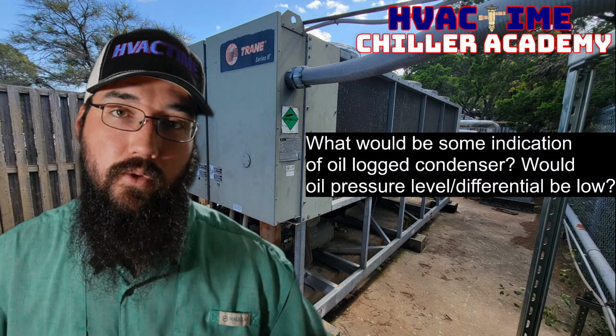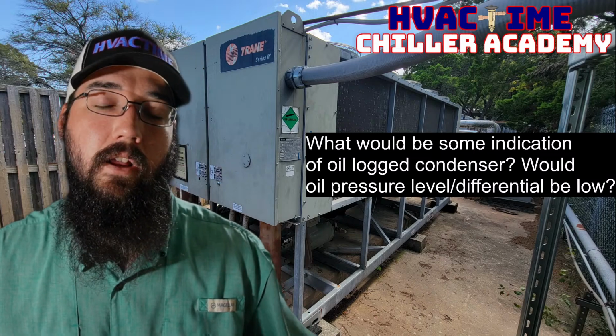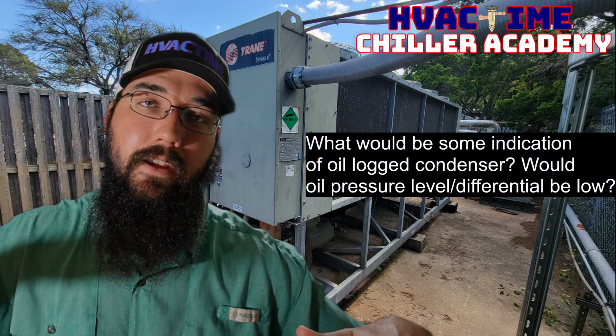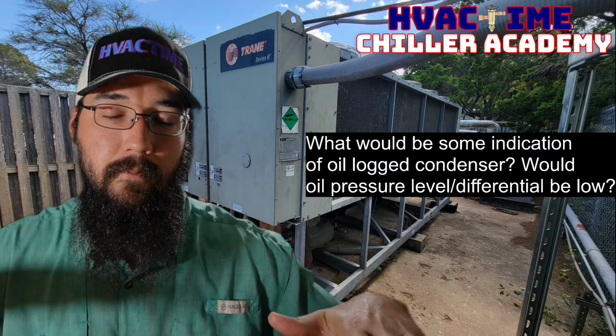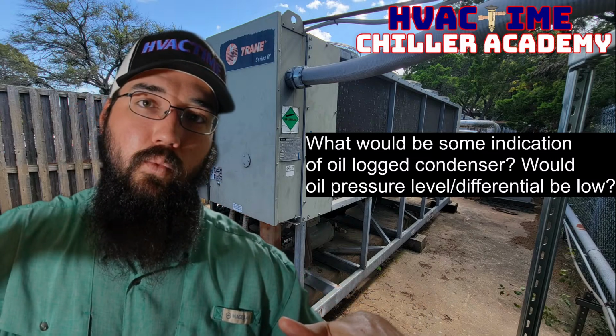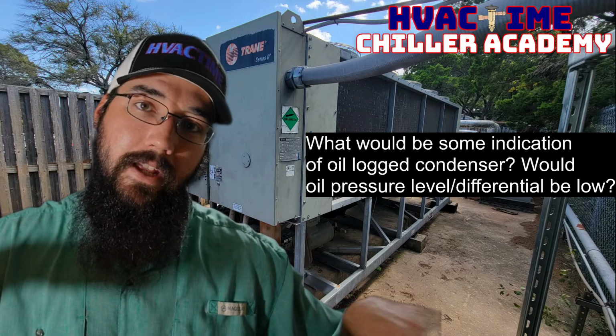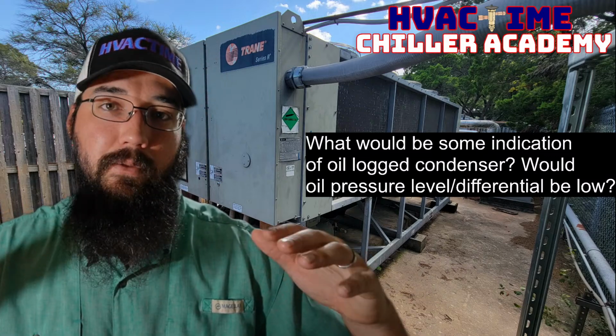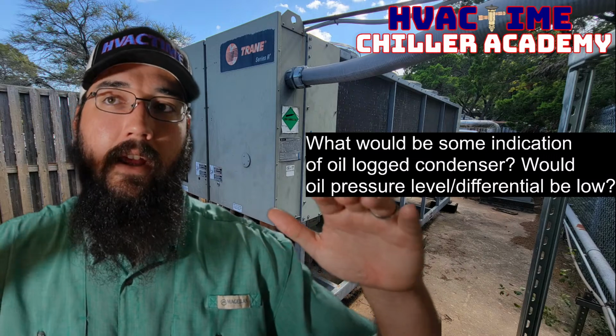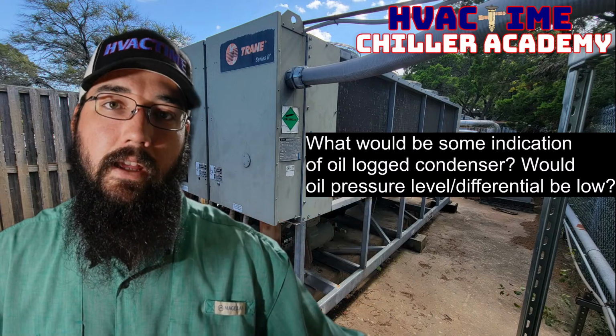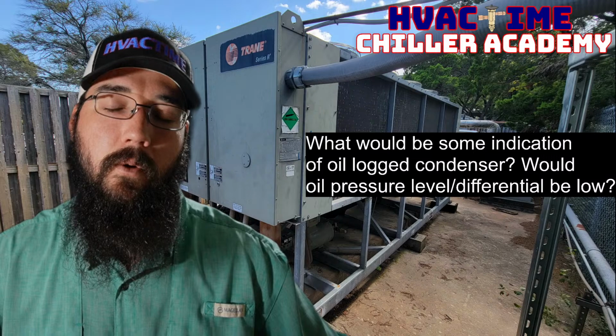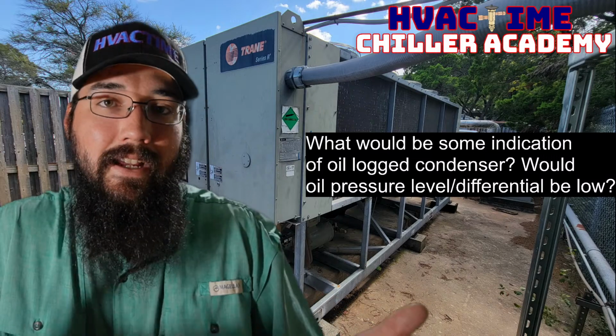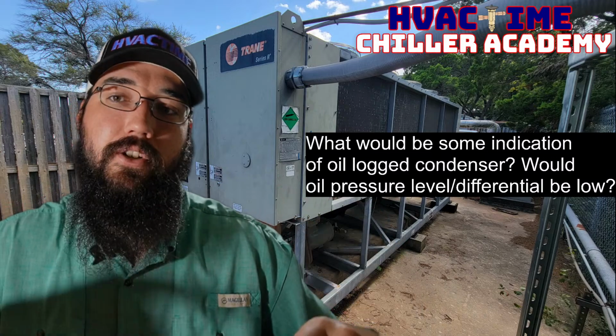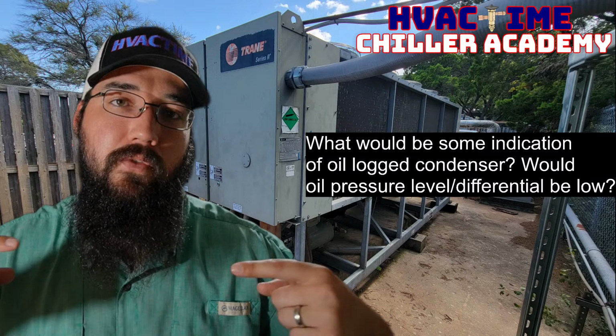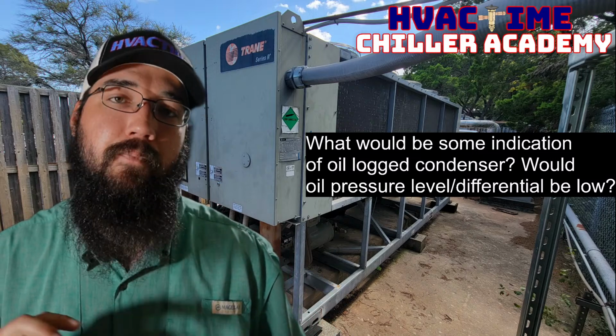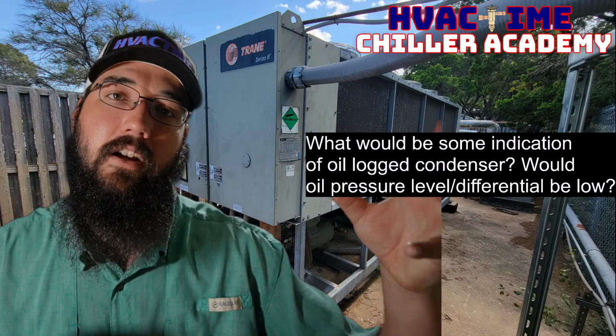This is true for air-cooled and water-cooled, but especially on the air-cooled side most of all. What I've seen with air-cooled is, if the system is not perfectly level, then whatever side it's tilted towards, the oil will naturally collect on that side. And especially in a low ambient condition or something of that nature, when our condenser coils are cold and our condenser saturation is very low, if we don't get that saturation up, we inevitably reduce how much velocity we have through that heat exchanger, and we're not going to be able to push those little pockets of oil that stack up in the condenser properly.